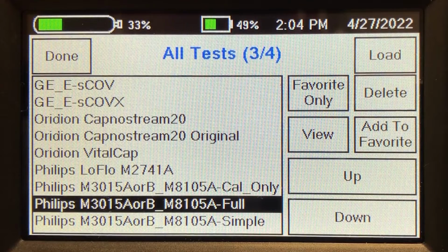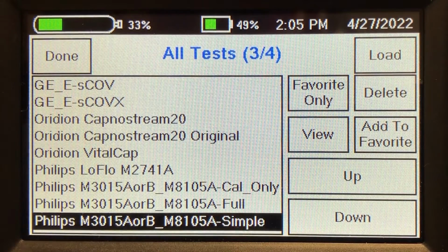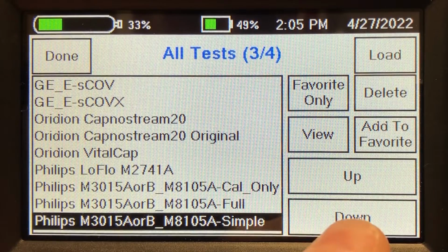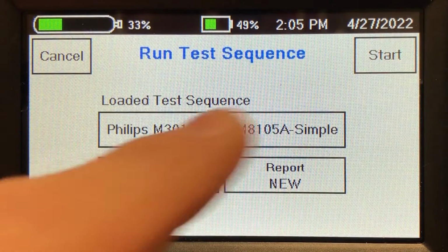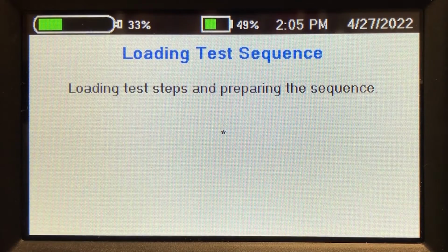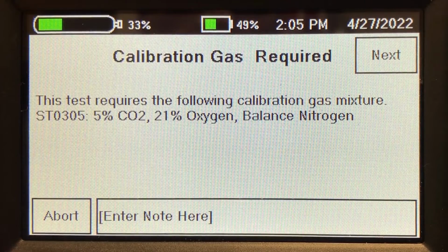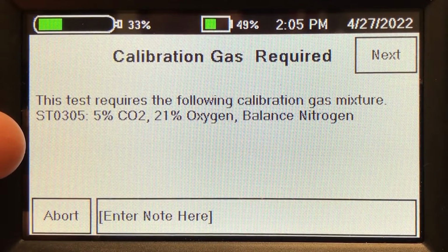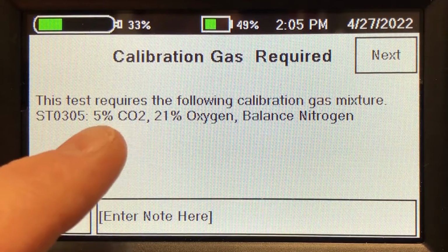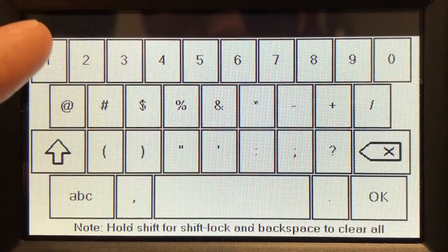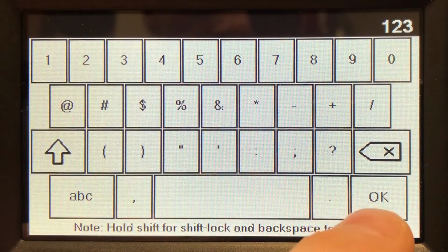It uses their slower leak down method for testing for leaks, and it includes a span gas check at the end of the test with 10% gas. So we'll do the simplified because it's most commonly used out there. Hit load and start. First screen tells us what calibration gas we need, and this one only requires the 5% CO2, 21% oxygen.